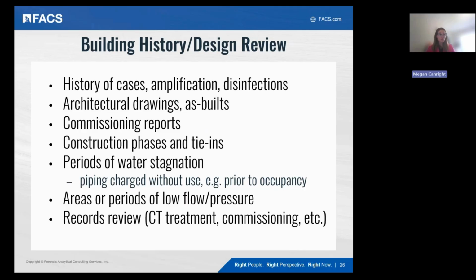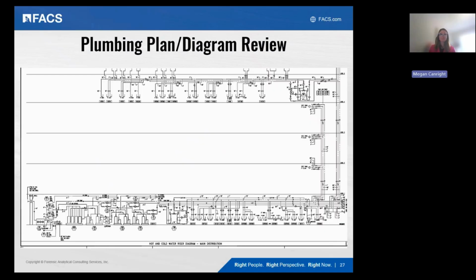Have there ever been periods of water stagnation, meaning the piping was charged without beneficial occupancy? We look at areas or periods of low pressure or low flow. Ideally we also review records—if the building has a cooling tower, for example, is it treated, and are there regular records of its management and treatment?